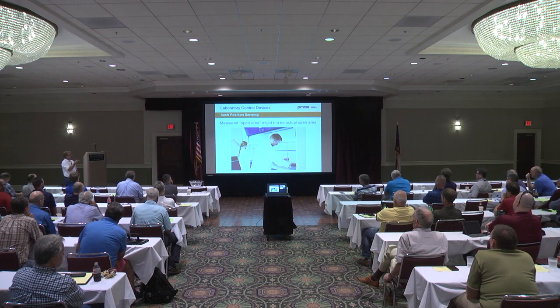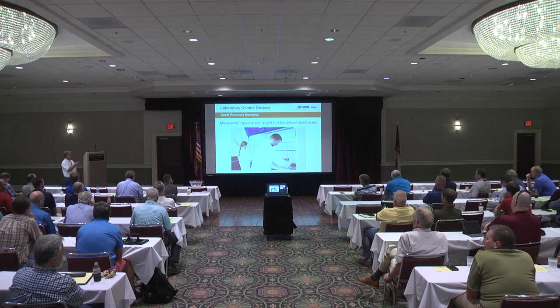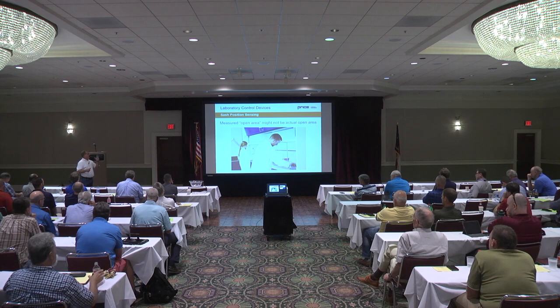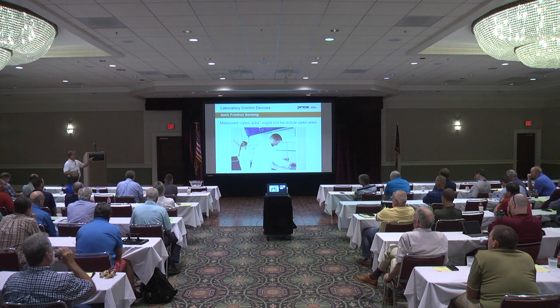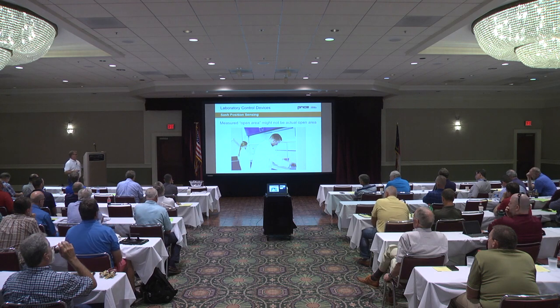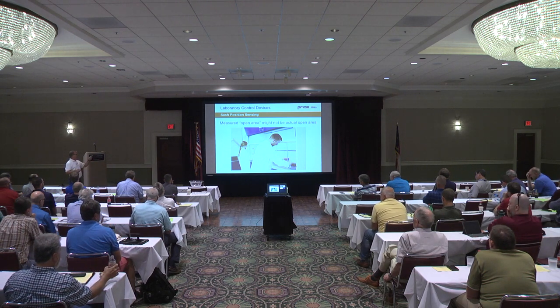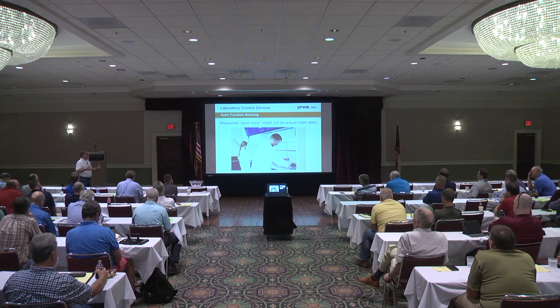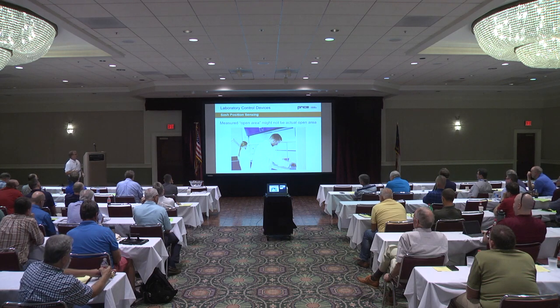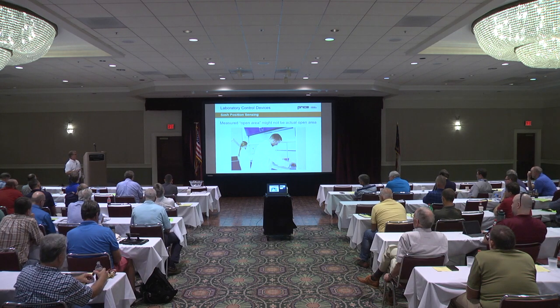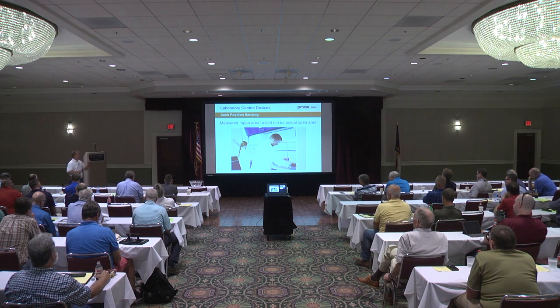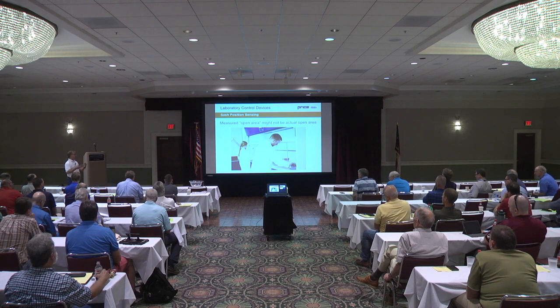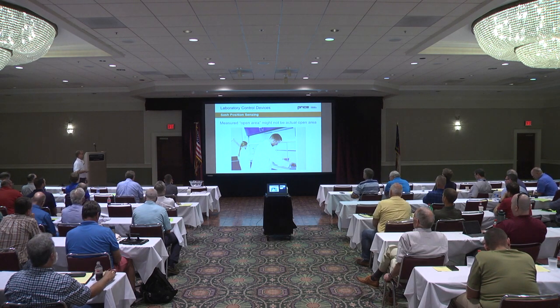When it comes to controlling fume hoods, you've got different areas based on the design of the hood itself. So we have a combination hood here where you've got the airfoil at the bottom, which is some amount of area. You've got your horizontals, which is some amount of area. And if they had a bypass louver on this hood, we'd have air flowing through the louver too, because until you raise it vertically, the louver wouldn't be closed off. So you'd have air going through that way. So the actual area may not be the open area of the sash.